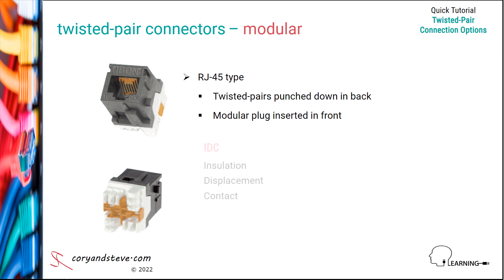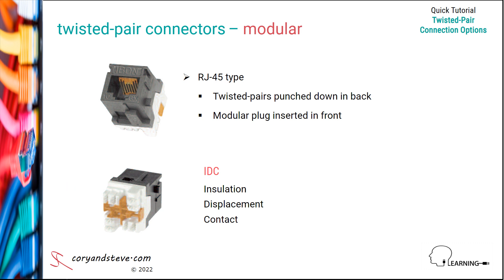The term insulation displacement contact or IDC is used to describe the punch down side, where a tool is used to push each of the eight wires in a four pair cable into a V-shaped connection point. As the wire goes in, its insulation is cut or displaced, making a metal-to-metal contact between the copper conductor and the connector.